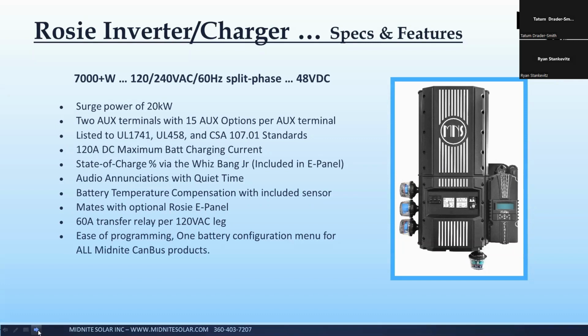The mobile Rosie, we'll talk about that in a little bit, but the mobile Rosie has some cool adaptations as well. It will auto detect 120 versus 120/240. So if you're in a big RV and you've got the mobile Rosie and you plug into a 30 to 50 amp dog bone, it will detect that the phases are in phase and it runs on both phases like that, in phase. Or if you plug into, well, very soon now, two legs of 208 three phase, which is actually more common in an RV park than one might think. We just found this out, actually. It will auto detect the 208 and run on that as well. So the mobile Rosie has a little flexibility in that.